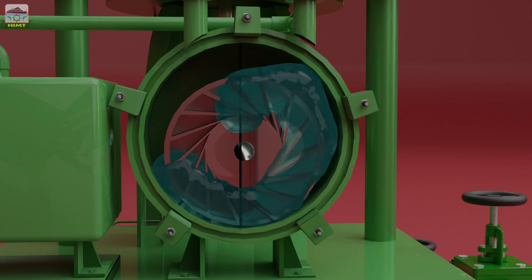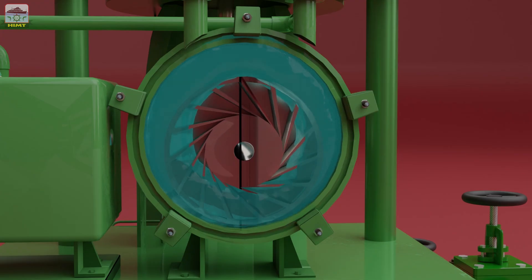When the rotor turns, the water inside the casing is thrown outwards centrifugally. The rotor churns a rotating ring of liquid to form the compression chamber seal.